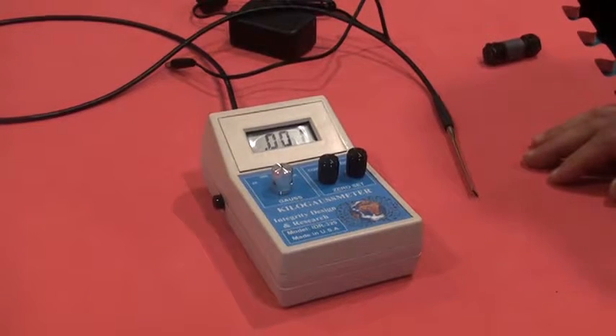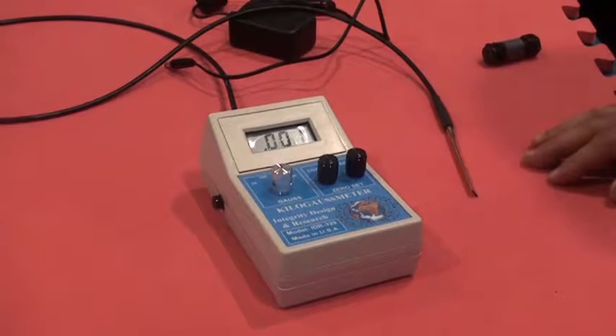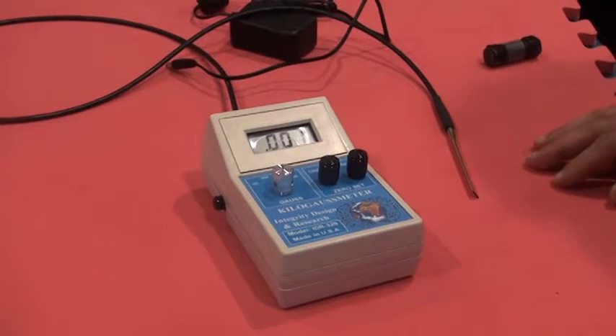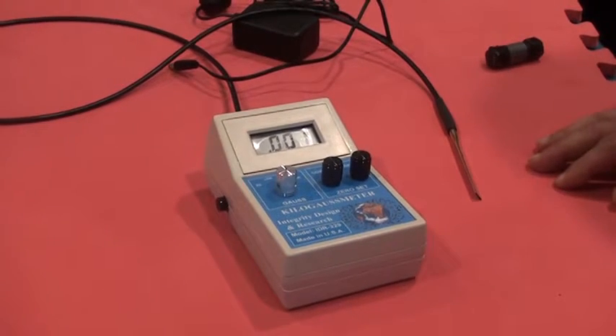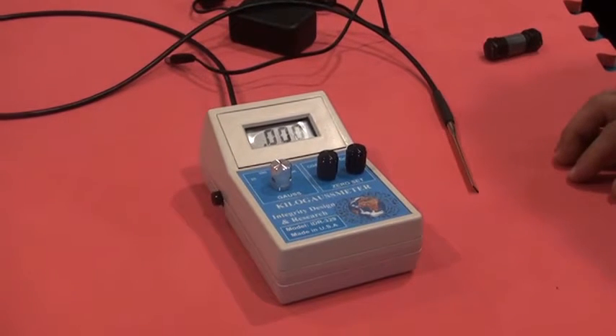I hope I was able to explain what you're looking for. Also keep in mind the calibration will usually be valid for 1 year, and we charge $95 with a data sweep, and we sweep from 20 Gauss using a Helmholtz coil up to 14,000 Gauss.